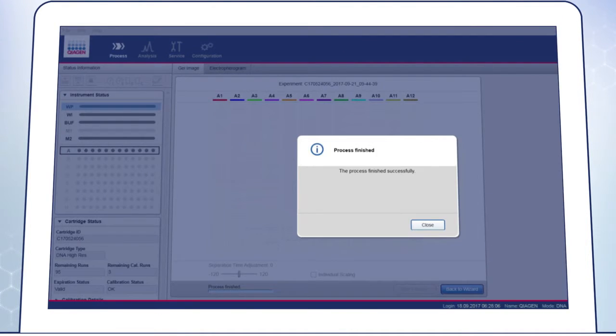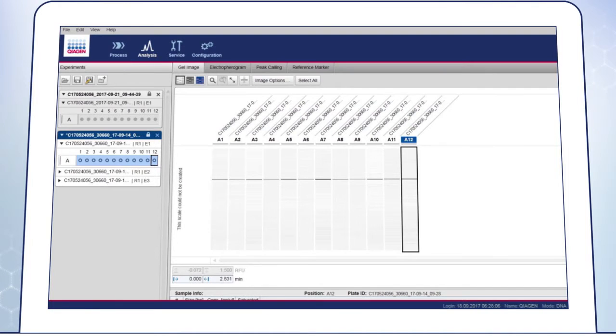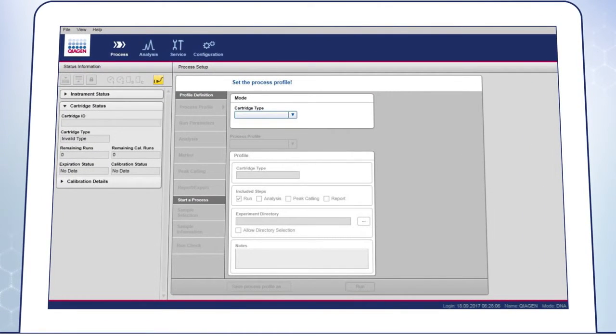If a single peak is detected in all channels, the intensity calibration can be performed again. If one or more channels failed to detect a peak, or if there is no band or several bands present, please contact QIAGEN Technical Services. In case any support is required, prepare the following data before contacting QIAGEN Technical Services.